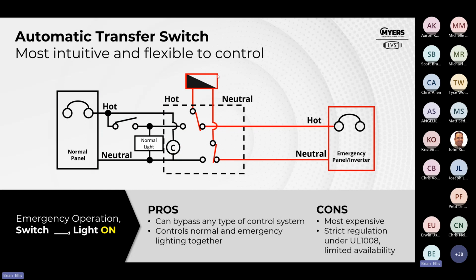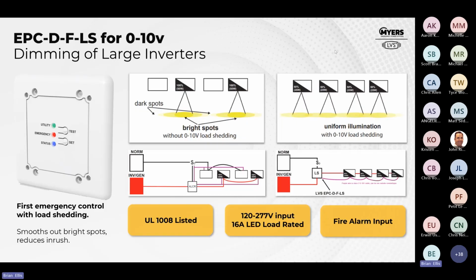So this not only gives you redundancy, being able to switch back and forth, but a lot of times where I see this is multifamily, like corridors and things, where the design might be calling for 0 to 10, but the owner provided some kind of decorative incandescent screw-in LED replacement. If that's the case, and you have a lighting control device and half the fixtures are normal, half the fixtures are emergency, your regular ALCR is not going to do the trick. We've got to switch over to the transfer switch. Okay, so this is a true UL1008 transfer device. And again, the reason is it transfers between one source and another.